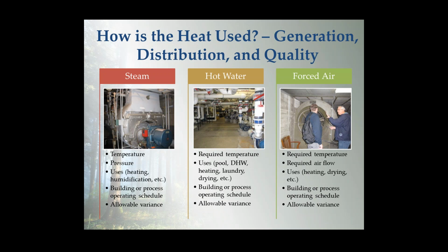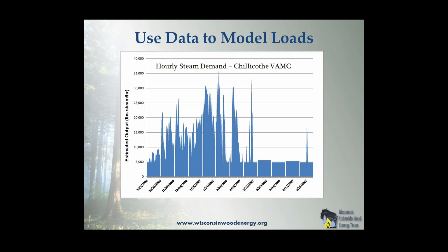Finally, forced hot air systems. We can use existing forced hot air furnaces and build in heat exchangers, but we need to know the temperatures that are required, what the airflow in those systems needs to be, what processes they may be serving, what parts of the building, and what kind of variability there is in those demands across the day and across the year. So we use that data and model the loads.